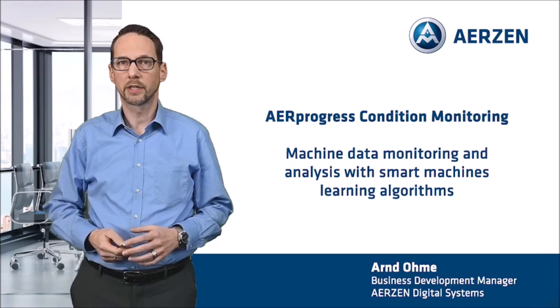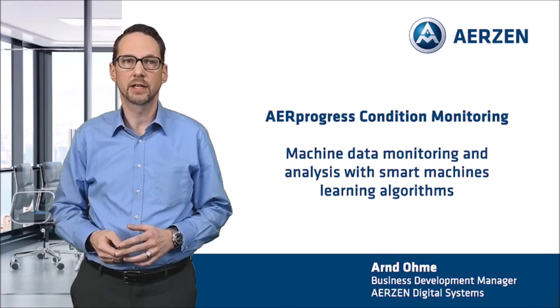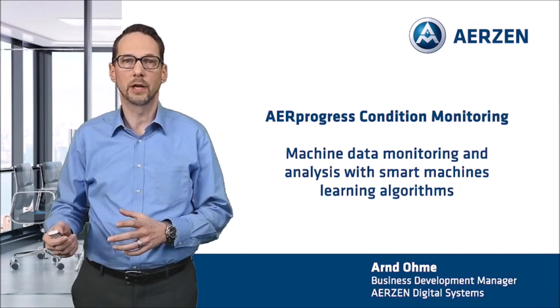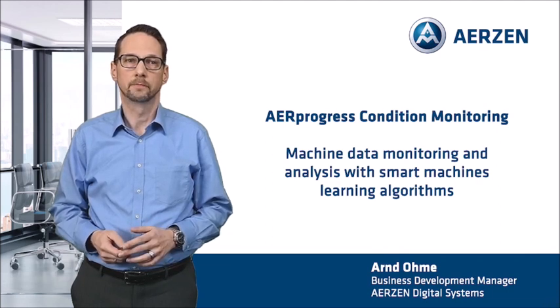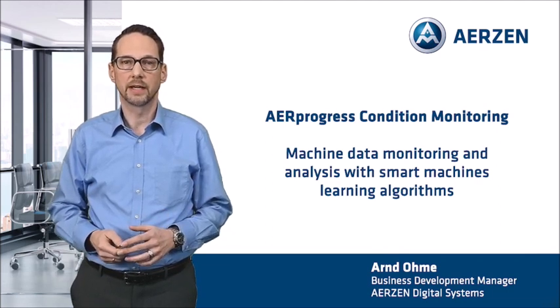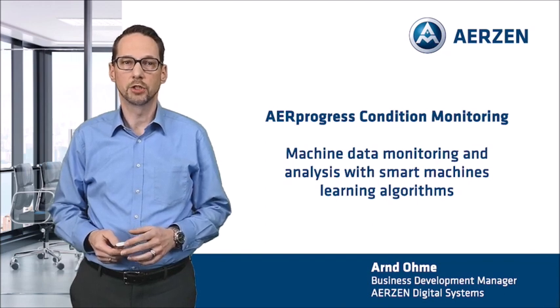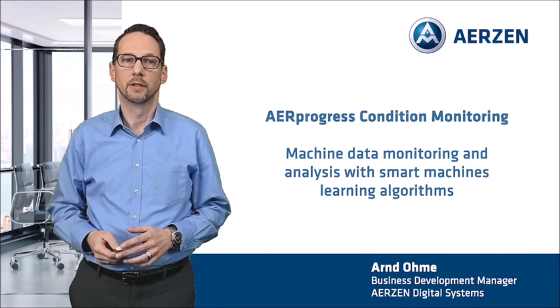With our product AERprogress condition monitoring, we collect the machine data like pressure and temperatures together with the vibration at the bearing of the stage and the engine. This data is analyzed with modern algorithms and the health index of the machine as a whole and individual wear parts are calculated from it.